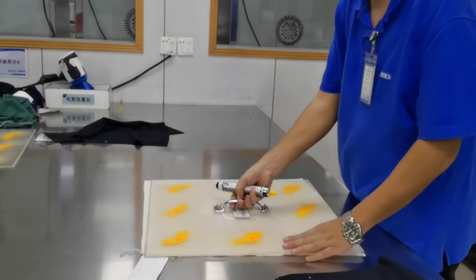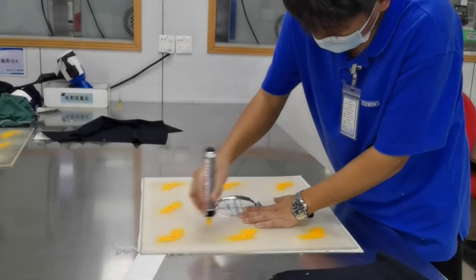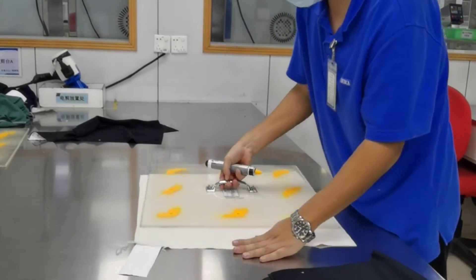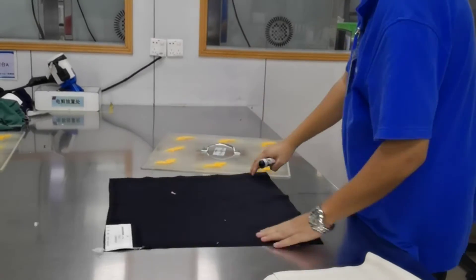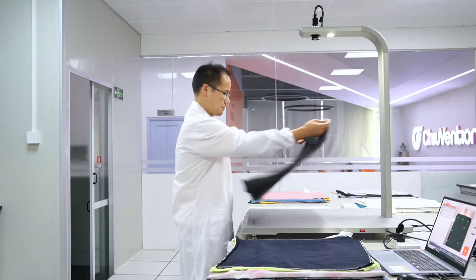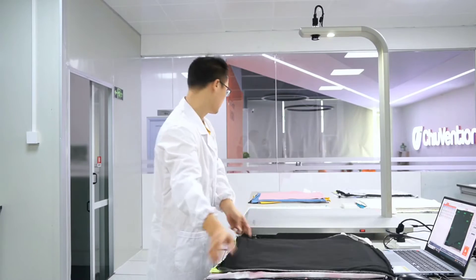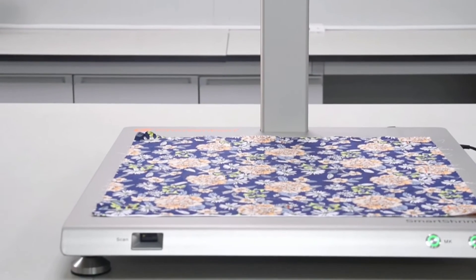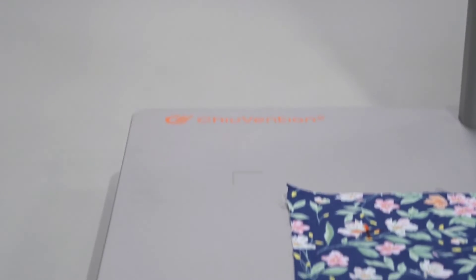In the advanced method, we start by marking eight dots on the sample using the provided template. These eight dots are equidistant from each other, which helps in the further testing process. Place the sample over the platform of the equipment below the high-definition camera sensor and press the MS button. The device will automatically measure the distance between the marked dots through a unique algorithm, and shrinkage rate is calculated, providing real-time accurate results.